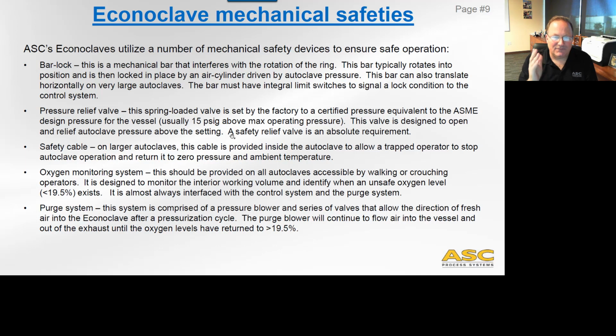So 19.5 is that OSHA safe level, and that's interfaced with the control system and the purge system. And the purge system is basically a pressure blower and a valve which is used to direct fresh air into the autoclave after a pressurization cycle. The purge blower will continue to flow air in until we get to 19.5%. So most large autoclaves, or really all large autoclaves, should have an oxygen monitoring system and a purge system if they are pressurized with nitrogen.